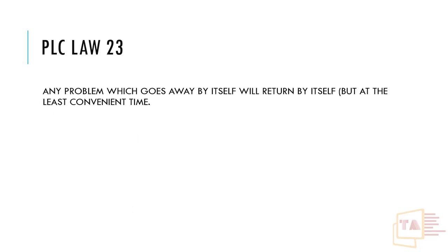Any problem which goes away by itself will return by itself — but always at the least convenient time. For example, if you go to a machine and say it is a sensor problem, you check the sensor and it looks correct, so you leave. Then again the sensor problem comes back. Monitor the machine — check signal quality, distance, and signal status to catch intermittent faults properly.